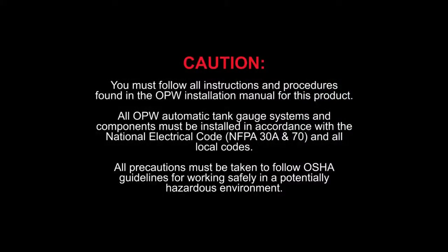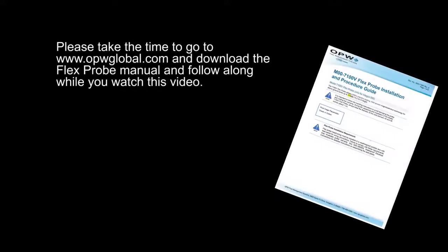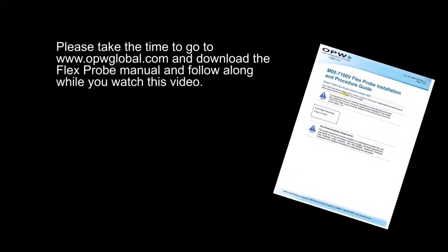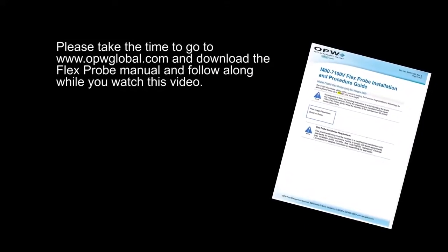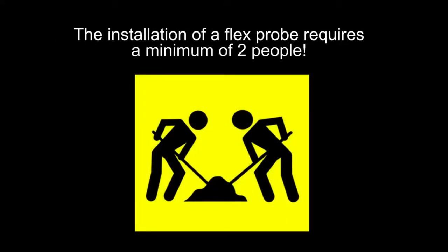You must follow all instructions and procedures found in the OPW installation manual for this product. All OPW automatic tank gauge systems and components must be installed in accordance with the National Electric Code, NFPA 30A and 70, and all local codes. All precautions must be taken to follow OSHA guidelines for working safely in a potentially dangerous environment. Please take the time to go to opwglobal.com and download the Flex Probe manual and follow along while you watch this video. The installation of a Flex Probe requires a minimum of 2 people.